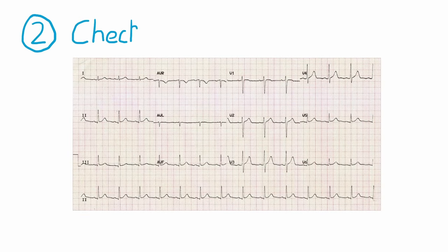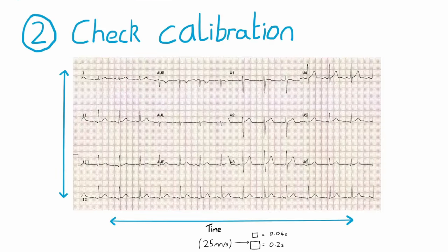Step two is checking calibration. This means checking the paper speed, which should be 25 millimeters per second. This speed will mean that one small square is equivalent to 0.04 seconds and one large square is 0.2 seconds. Also check the calibration of amplitude, which should be 10 millimeters per millivolt.